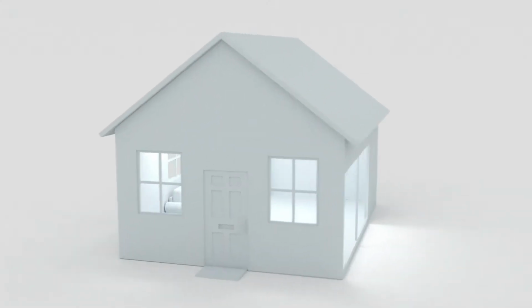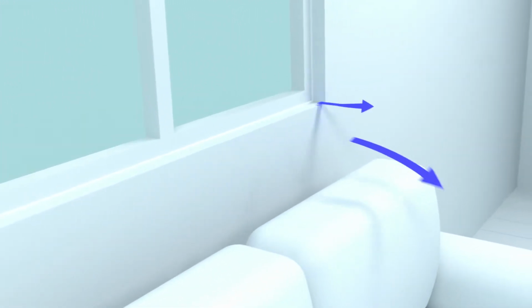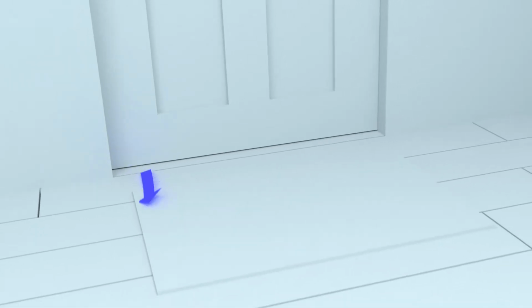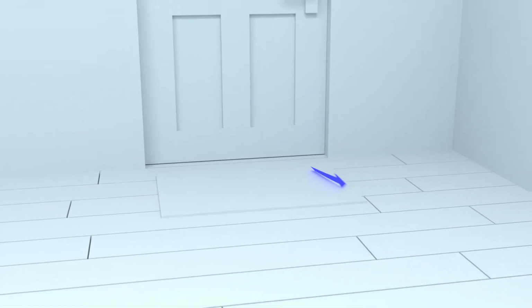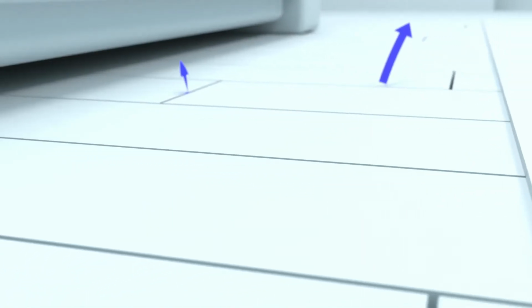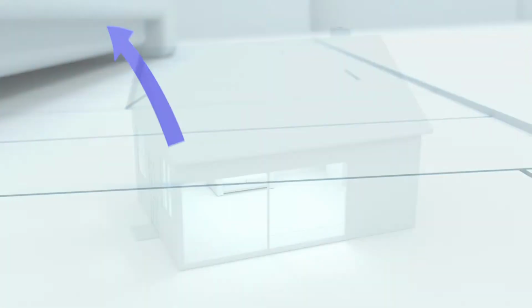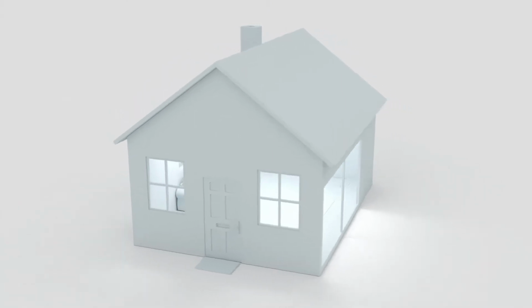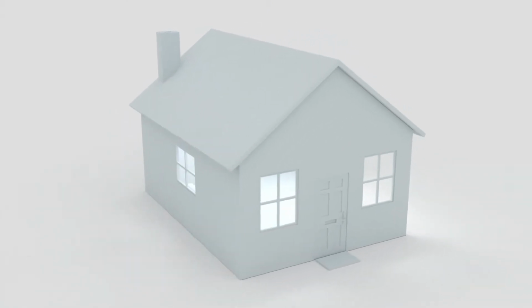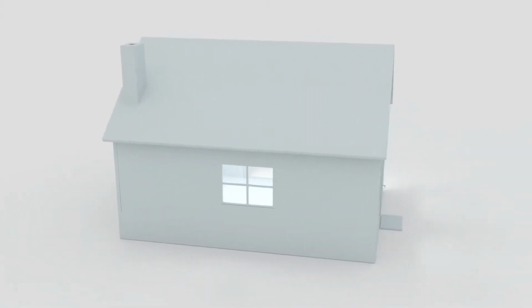Unintended air leakage in buildings can account for as much as a third of overall space heating demand. A building with high air leakage is drafty and uncomfortable, loses heat very quickly, and the indoor air quality is more prone to be affected by the outdoor environment. Conversely, a building with low air leakage is much more energy efficient, but at risk of being underventilated to the extent that it could suffer from indoor air quality issues.